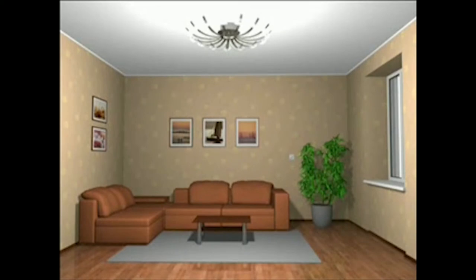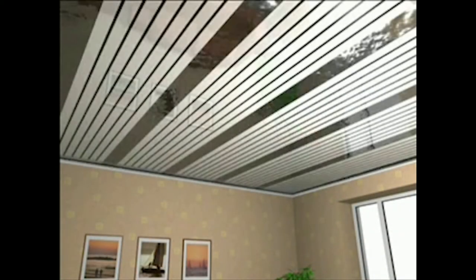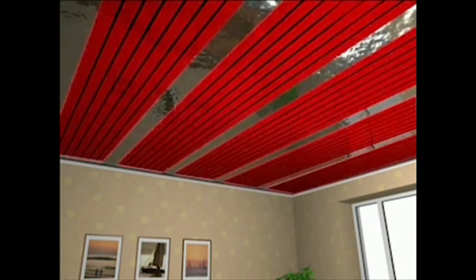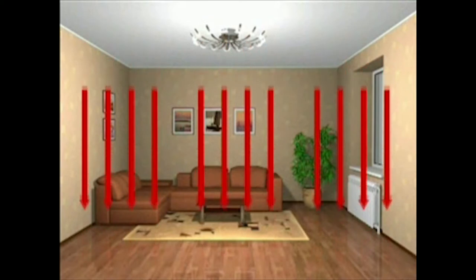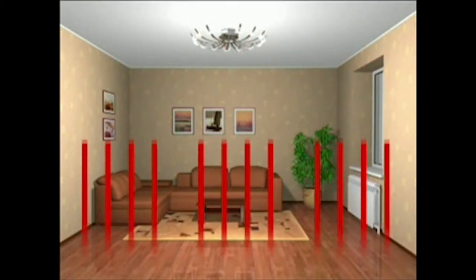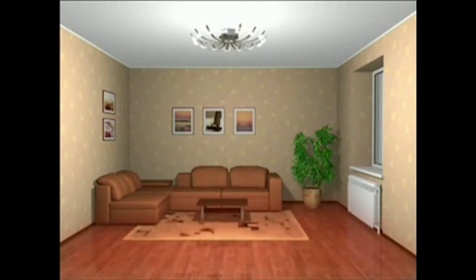All installation in an area less than 100 square meters will take less than one week. Step-by-step installation is also possible. When you supply electricity to PLAN, it achieves a maximum temperature of 40–42 degrees within a few minutes. Heat flow is transmitted to the floor surface, which absorbs it and is warmed up. The room gradually gets heated by the second heat transmission, and remarkably the maximum temperature is now at the floor surface.